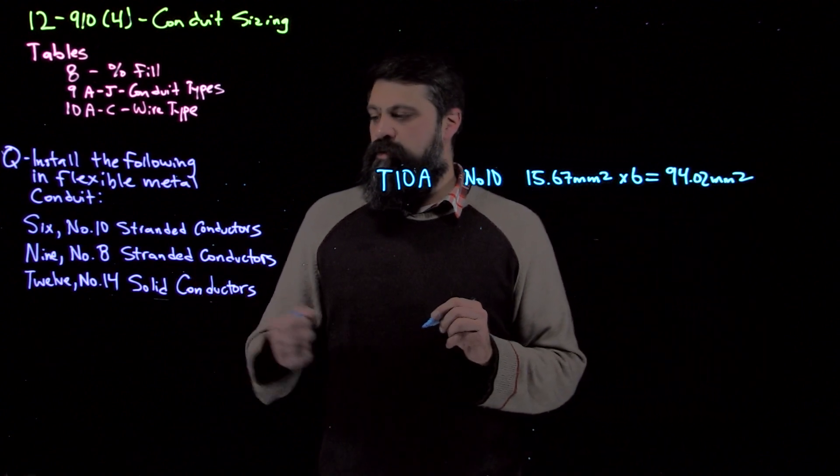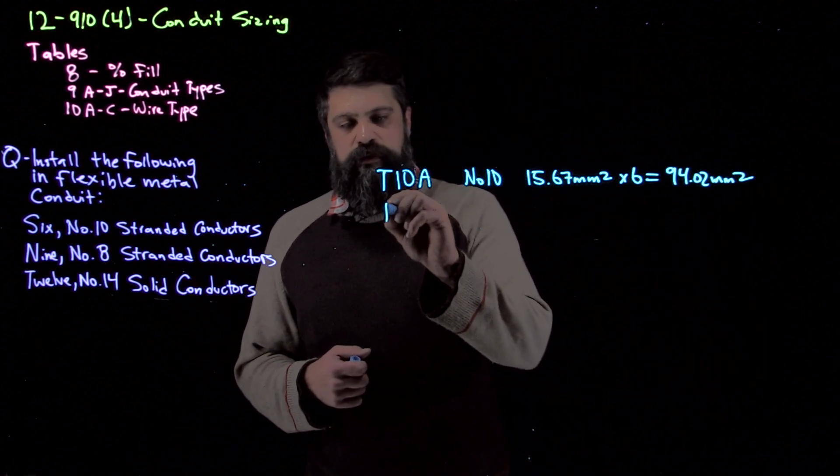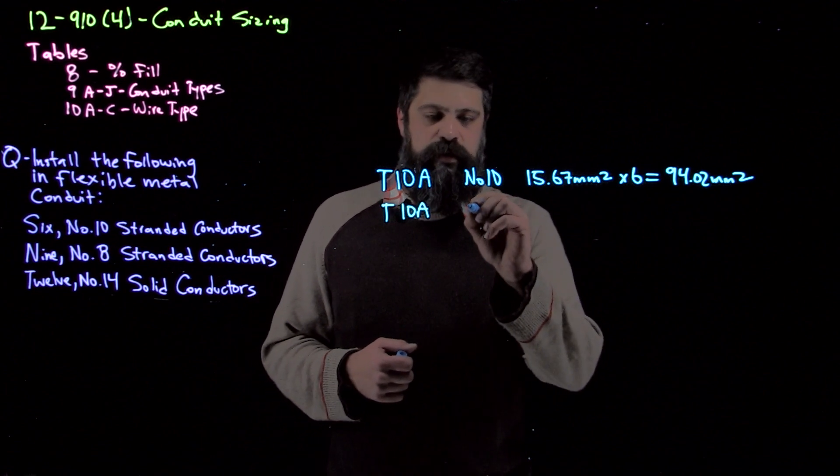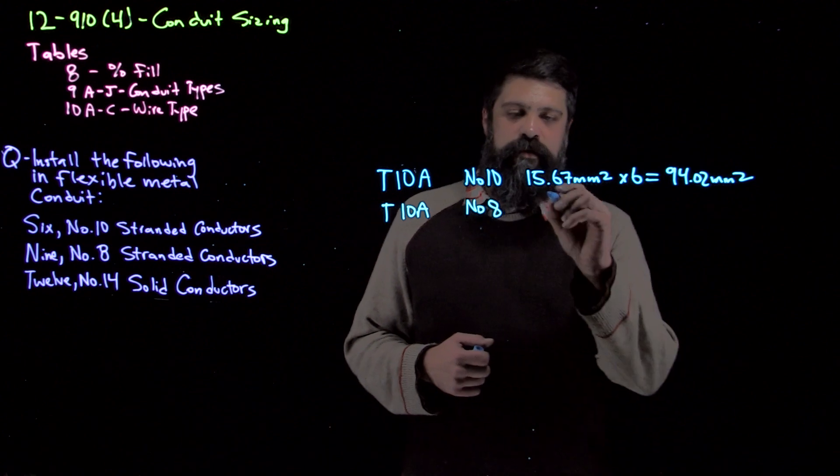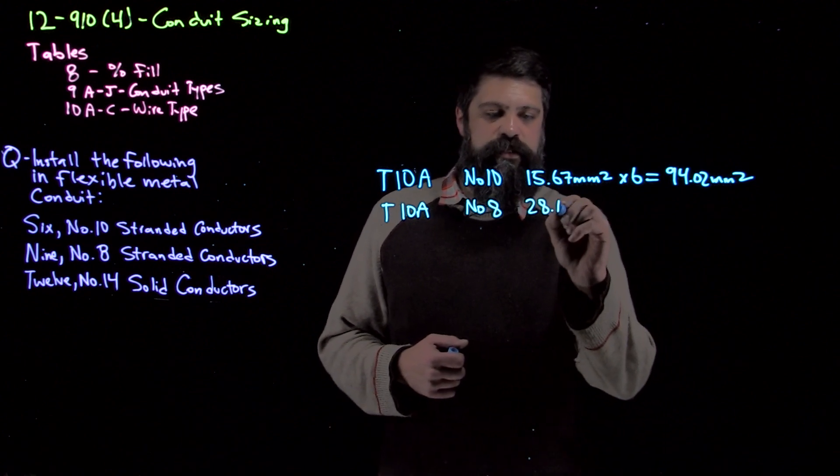Okay, the second one that we're going to do is number 8 stranded. So again, we're still going back over to table 10A. And now we'll look at number 8. Number 8, a single conductor, is 28.17 mm².